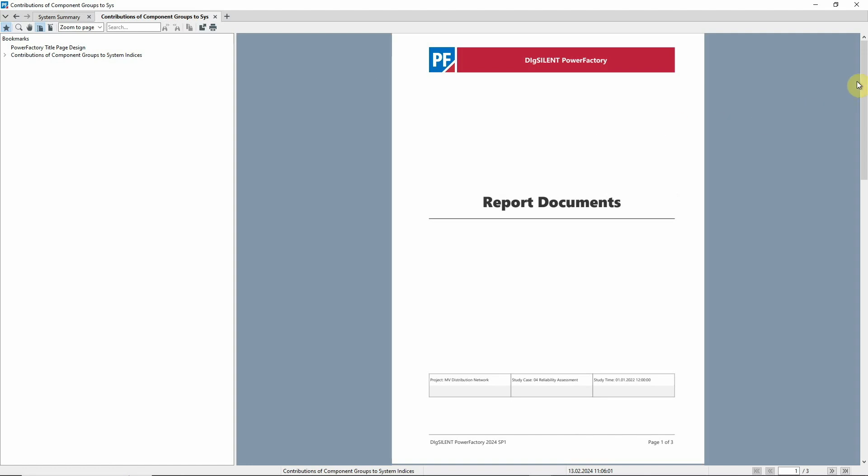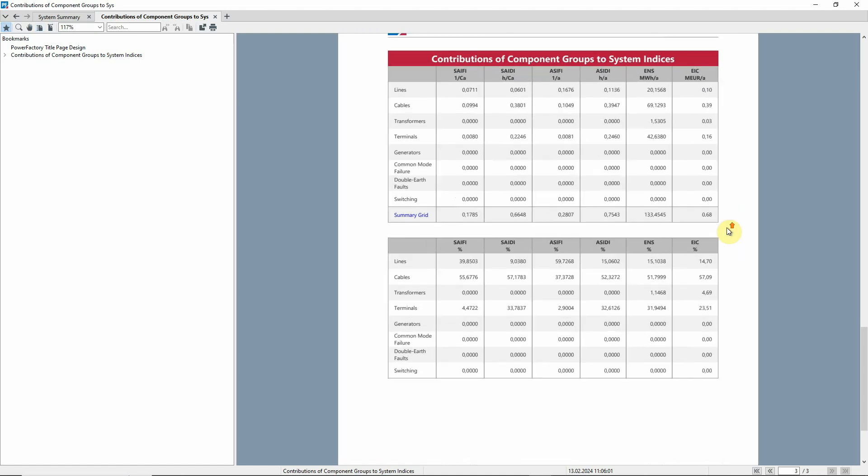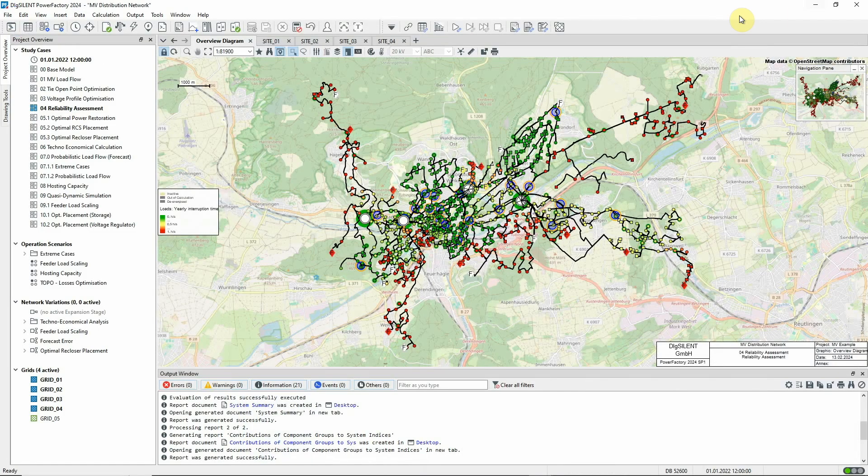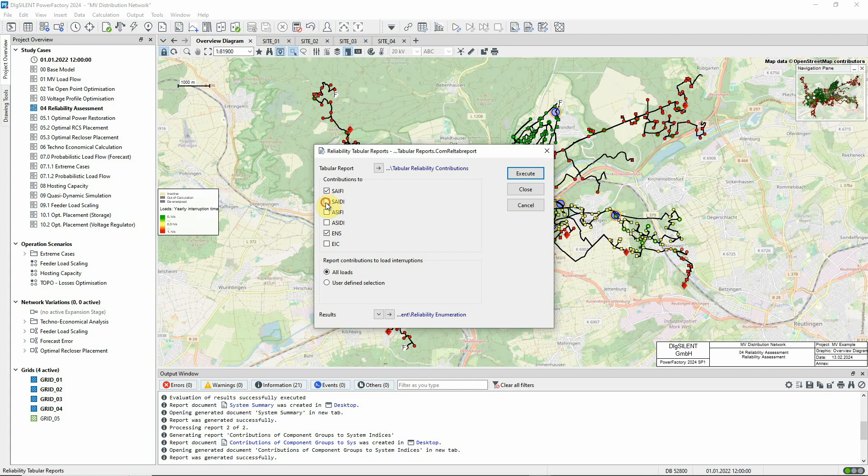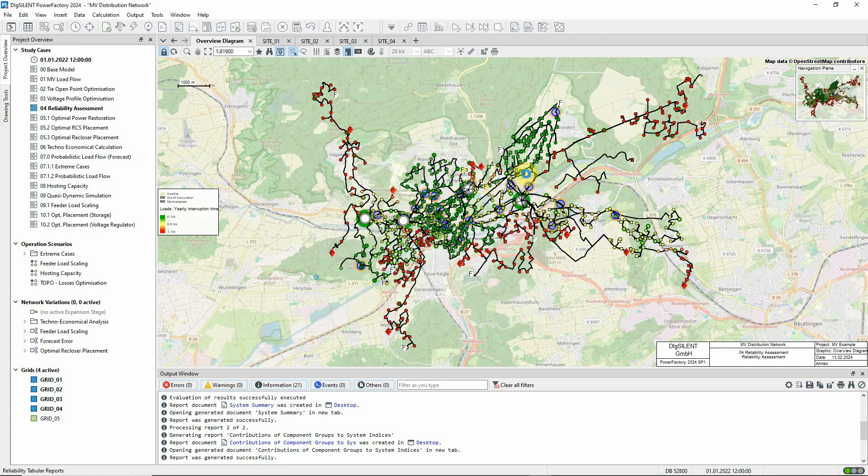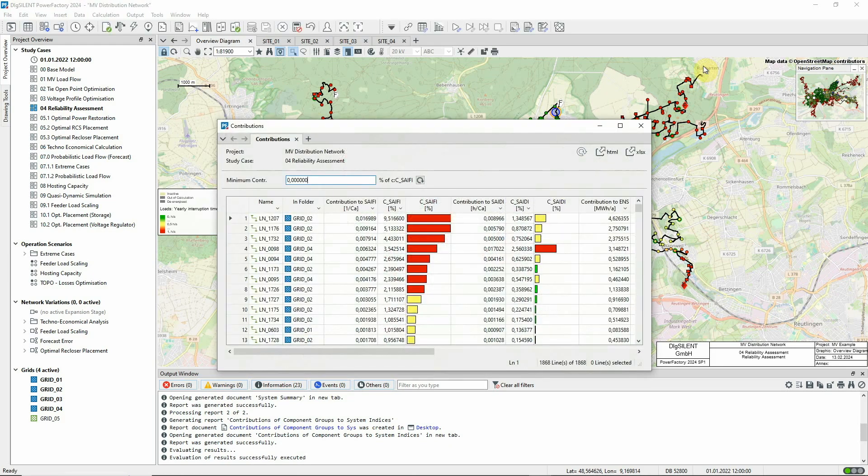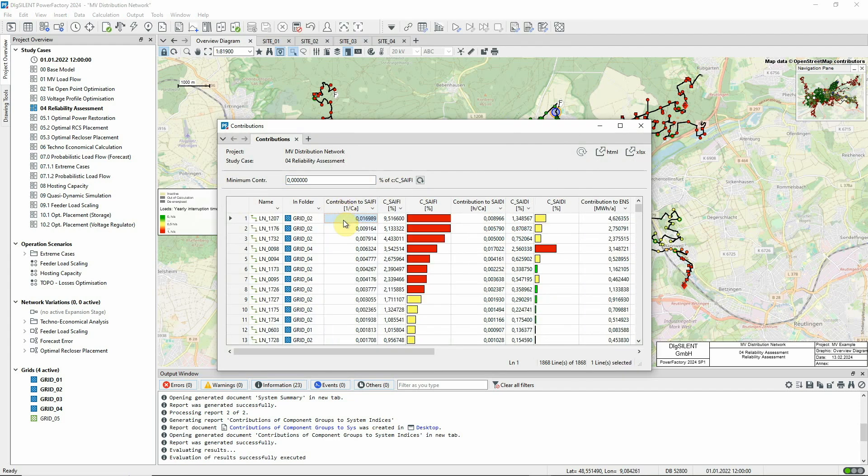This other report provides a breakdown of contributions to the indices according to the type of network component. We'd now like to know which particular faults are contributing the most to interruptions of supply. This icon can be used to create tabular reports of contributions. Let's look at these three indices. The table can be sorted as required. For example, we can sort to see which faults contribute most to SAIFI.